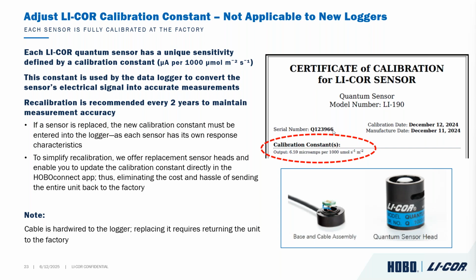So to simplify that recalibration process, we do offer quantum heads. So essentially, the sensor head can be disassembled and removed from the base and the cable assembly. So you could send out just the sensor head to be recalibrated, and we can send it back and then you can enter that calibration constant. Or to not stop your deployment, we actually offer new quantum sensor head, which you can purchase separately. And if that's the case, again, you need to enter that new calibration constant, and we've made sure that it is a feature that's available right on the app, and you don't have to use any additional software. And I'll quickly show how that works.